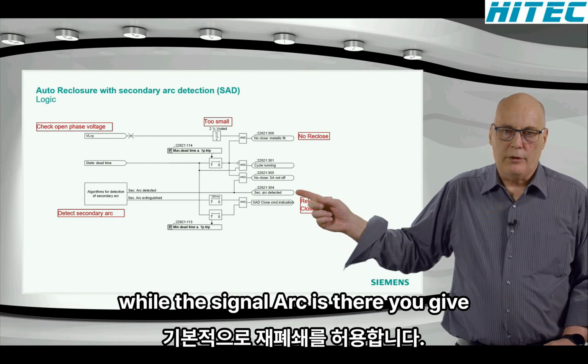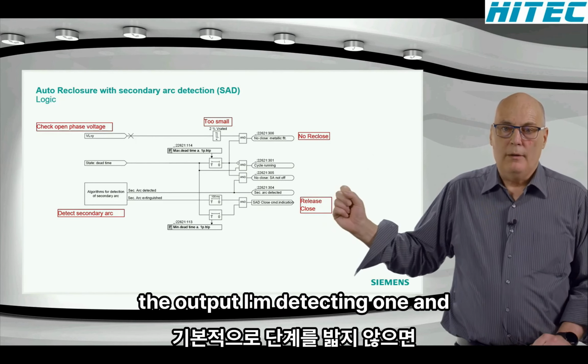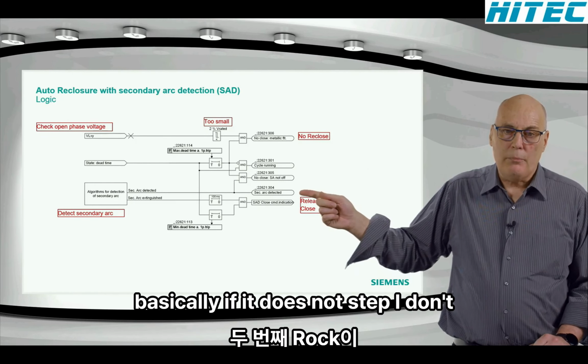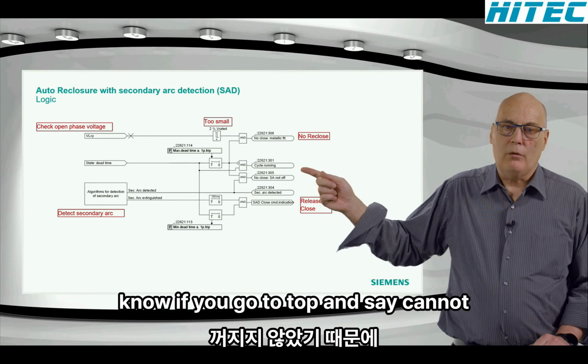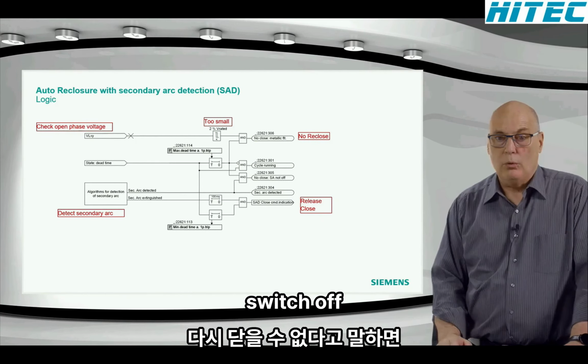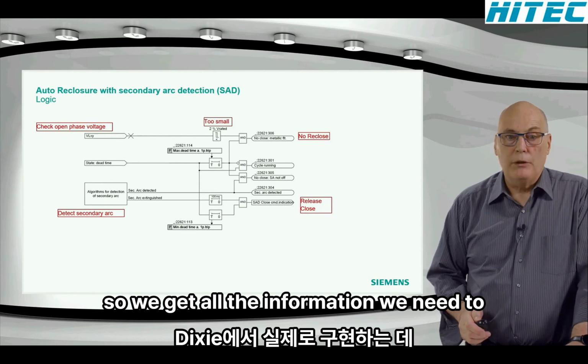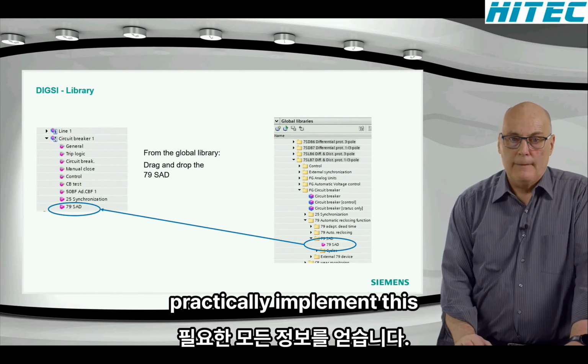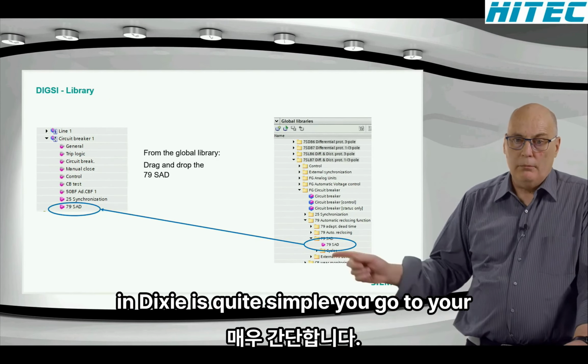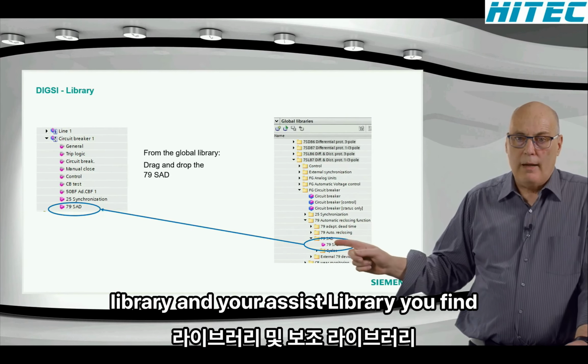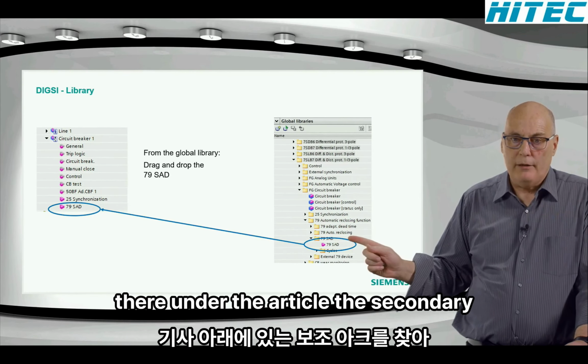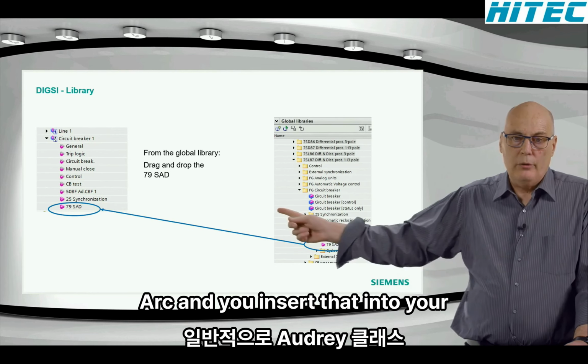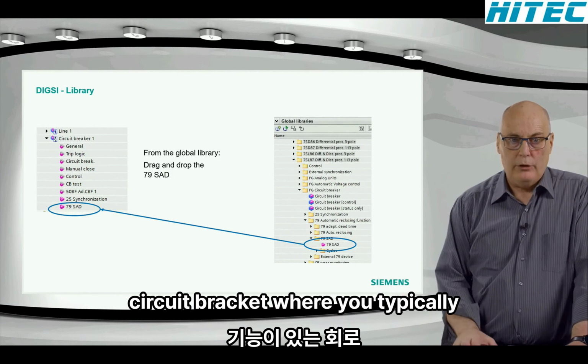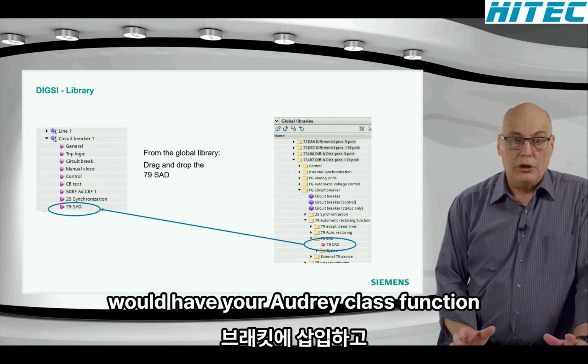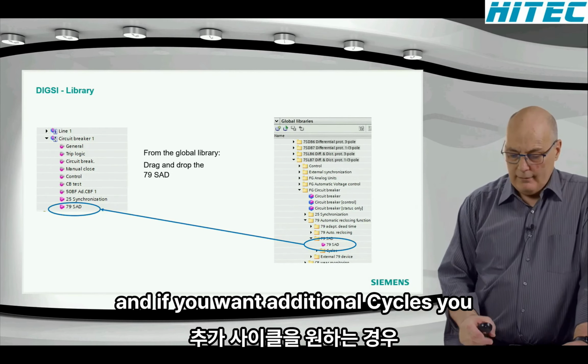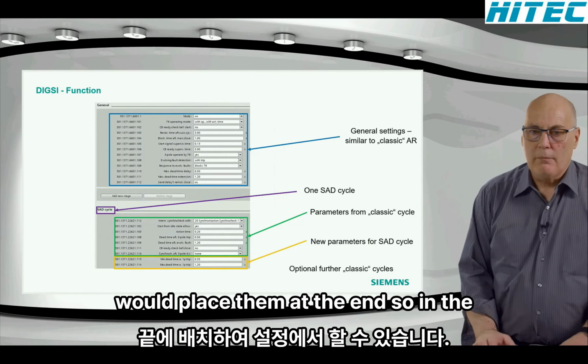While the secondary arc is there, you give the output, I'm detecting one. And basically, if it does not disappear, then obviously you go to the top and say, cannot reclose because the secondary arc did not switch off. So we get all the information we need to practically implement this. In DIGSI, it's quite simple. You go into your library, and your system library, you find there under the auto reclose the secondary arc, and you insert that into your circuit breaker where you typically would have your auto reclose function. And if you want additional cycles, you would place them at the end.